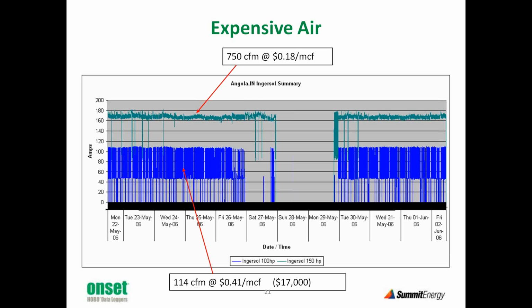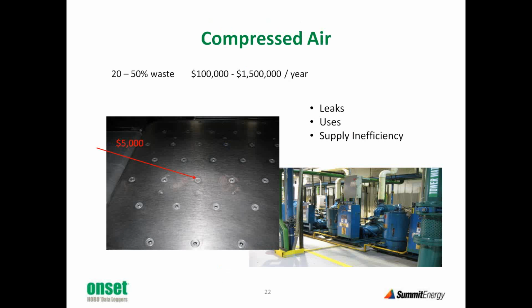Now, based on the HOBO data analysis, we know it costs $17,000 per year to operate that machine. And so the potential savings, if we could reduce our usage by 114 CFM, is $17,000. And it turns out it's not that hard. Those of you that have seen leak tables, you may be able to go out and just fix 4 or 5 leaks, and that second machine would shut off.